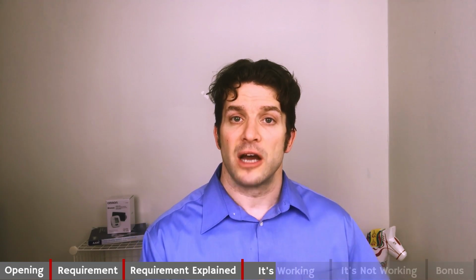How do I know this is working? Well, first, I have a procedure that clearly defines how I control, review, evaluate, segregate, investigate nonconforming product. Second, nonconforming product is clearly segregated away from conforming product. Third, I do my investigations. Fourth, if I disposition concession or rework, I meet all the regulatory requirements. So basically, I'm controlling my nonconforming product.